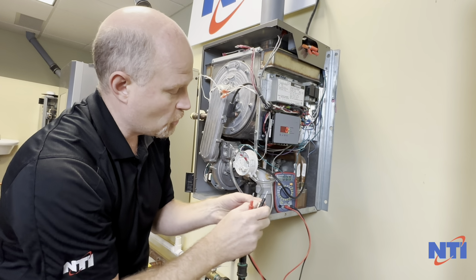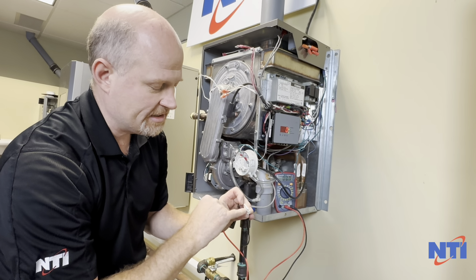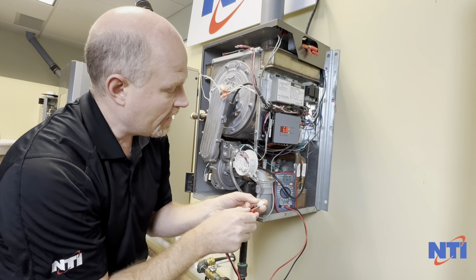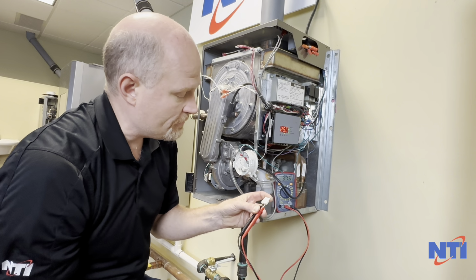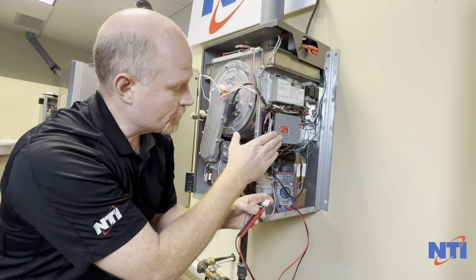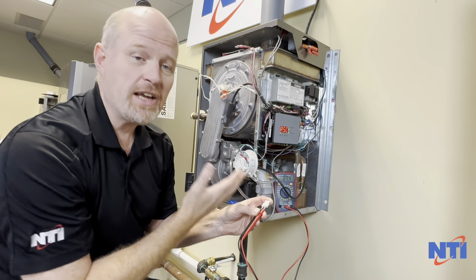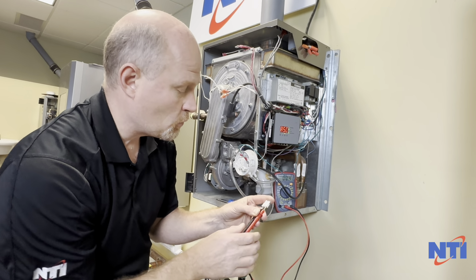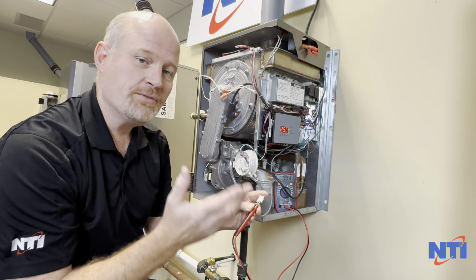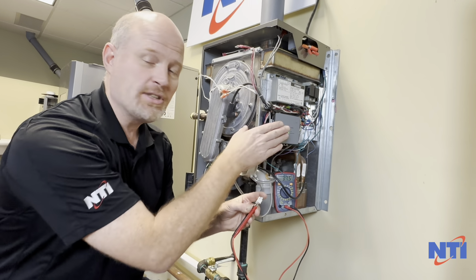We're going to back probe this connector, and usually it's best to use the back of the connector because it's easy to damage these pins. And when things are working correctly, if we see more than 35 volts DC, the Sentry control has told this blower to shut down, and if it fails to turn off, it's a bad blower. If for some reason your Sentry control is sending 12, 15, 20 volts, something less than 35, it indicates that there's something wrong with the Sentry.